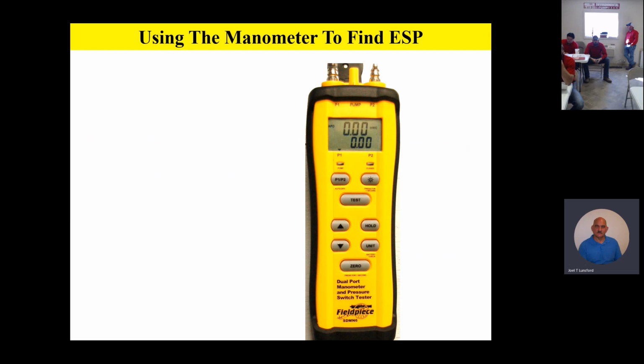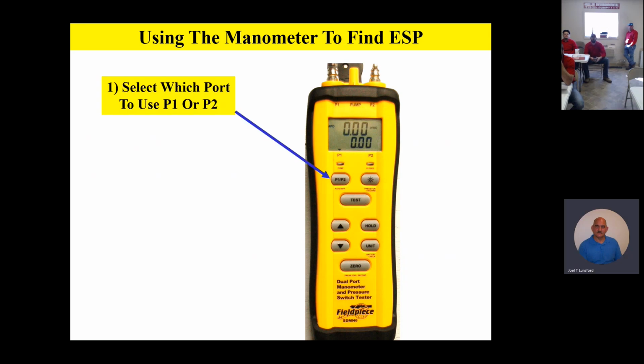To find external static pressure, we're going to use a digital manometer, or you can use the old Magnehelic gauge. But most people nowadays use a digital manometer, and this is just an example of one. There are a lot of different brands out there. I just happen to have a FieldPiece in my tool bag, so that's what you're looking at. You'll notice that it's a digital readout. You'll also notice there are two different ports on this, P1 and P2. So you select which port you want to use and make sure you hook your hose up to the port that you're using.